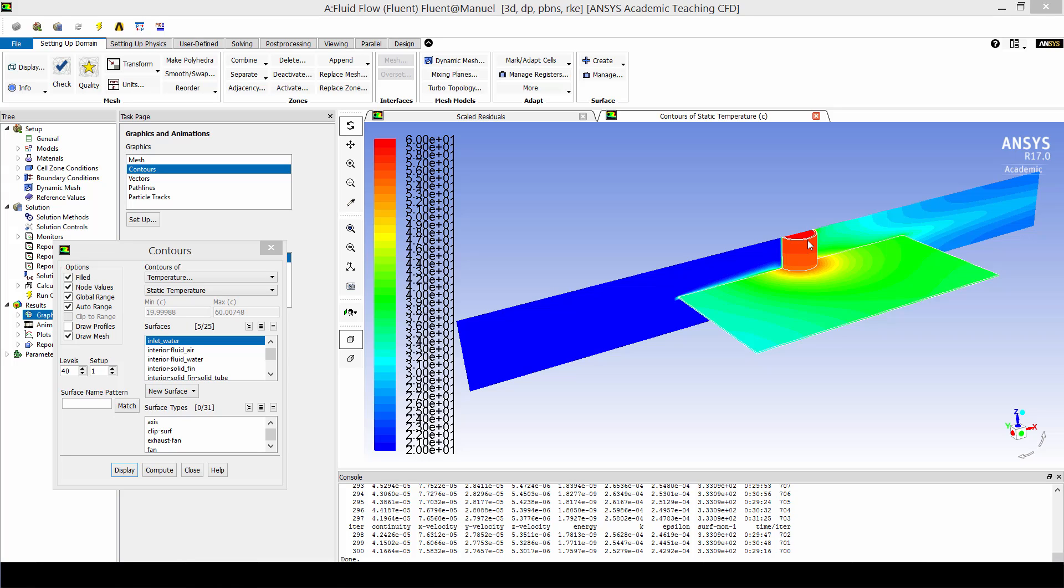So what is physically going on is that the water is transferring heat to the tube through the process of convection. Then the tube is transferring heat to the fin also through conduction. And then the cold air as it moves from left to right is picking up that heat through the process of convection. So as you can see here the temperature of the air has gone up as it goes around the tube and over the fin.